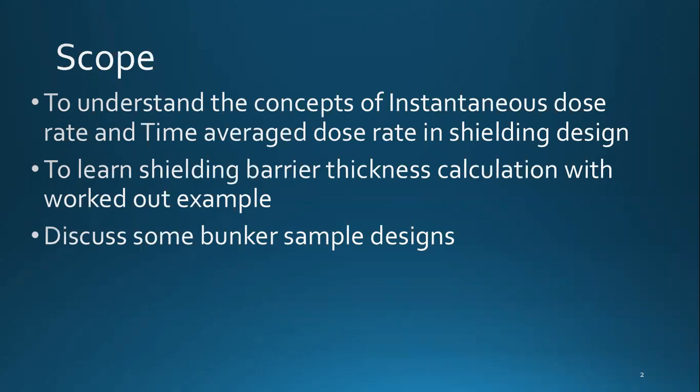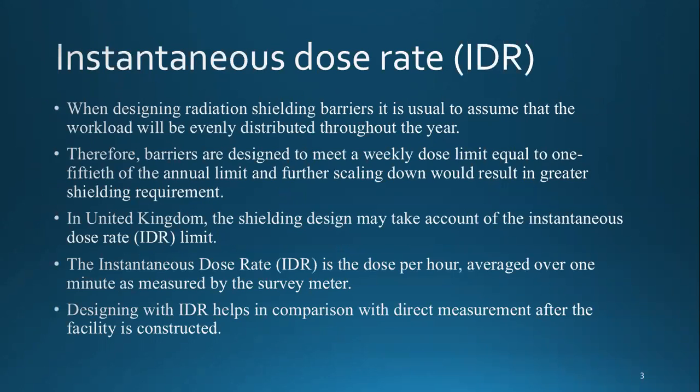I have also discussed some sample bunker designs for C-arm linear accelerator, which I think will be helpful for the student in his career. Let us look at what is instantaneous dose rate and its usefulness.